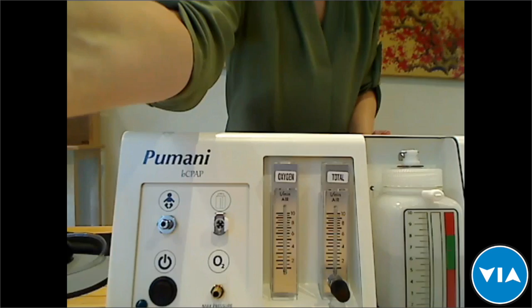Sure. There's currently not a battery backup, so we recommend that the Pumani is used in facilities that have fairly regular power or have a generator to provide backup power. There are fuses in the power cord as well as in the machine itself, so if there are voltage spikes, it's possible that the fuse in the cord or in the outlet on the back of the machine may blow, but that protects the machine, and we have spare fuses that can be replaced inside of this. There's a small drawer here, so that prevents damage to the machine if there are voltage spikes.